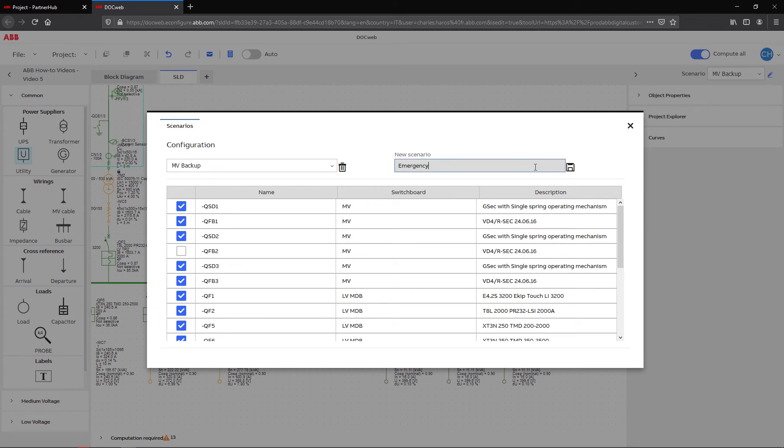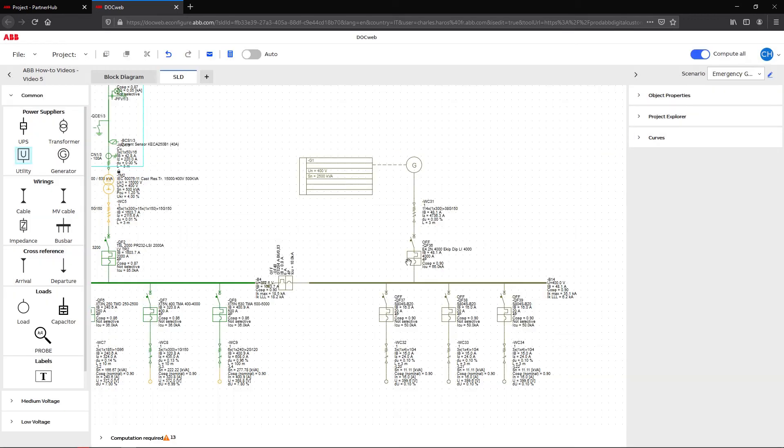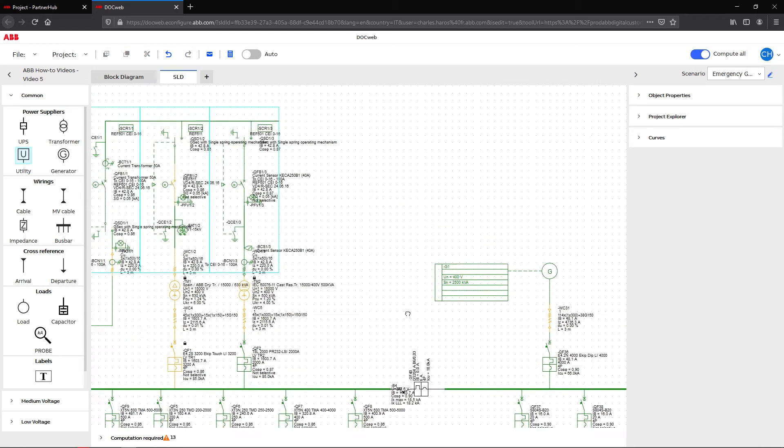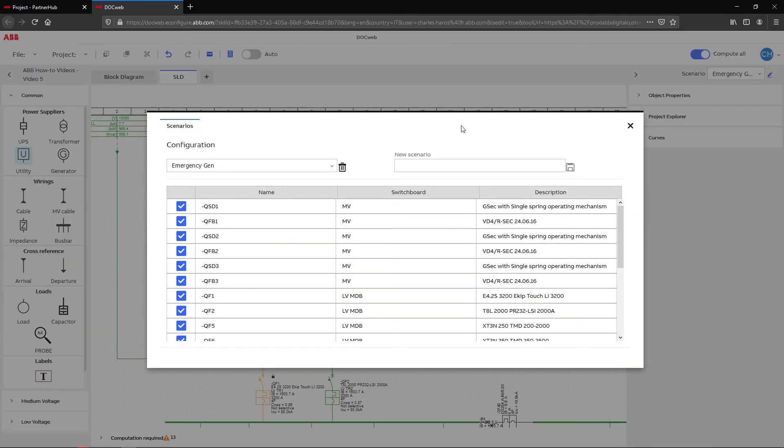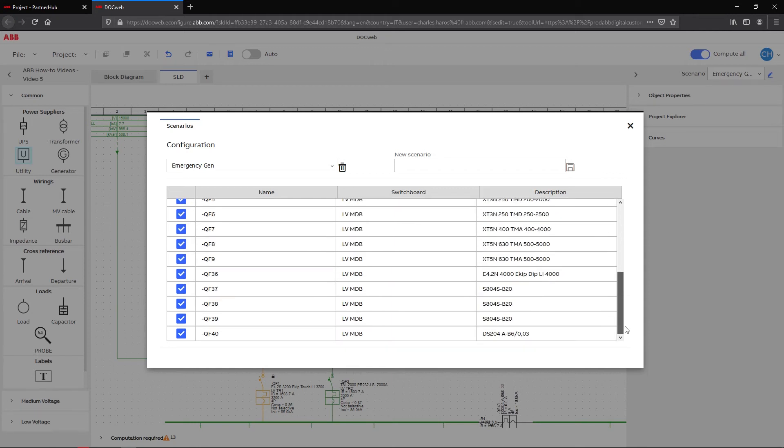To create a scenario where the emergency generator comes into action, start by deactivating the main incoming circuit breaker QFB1. The QF36 breaker must remain checked to activate the emergency generator and feed the priority loads.